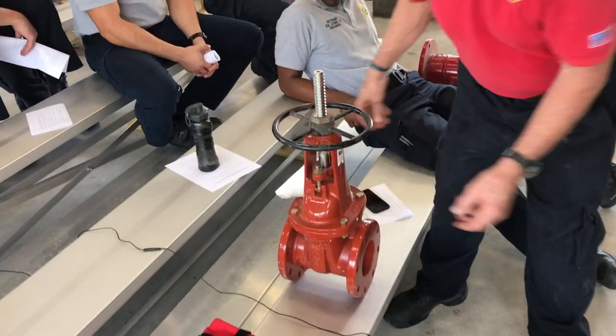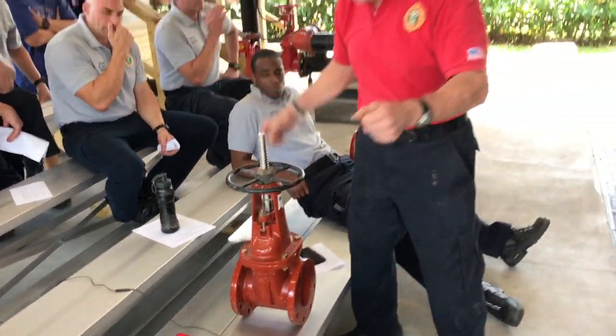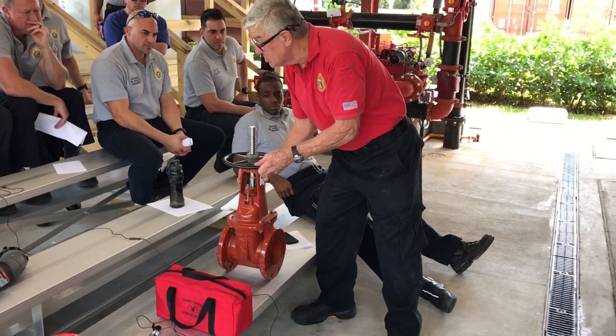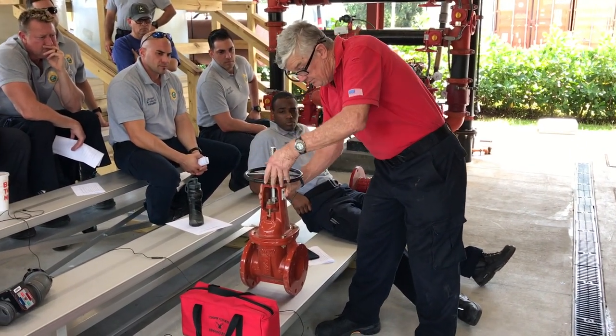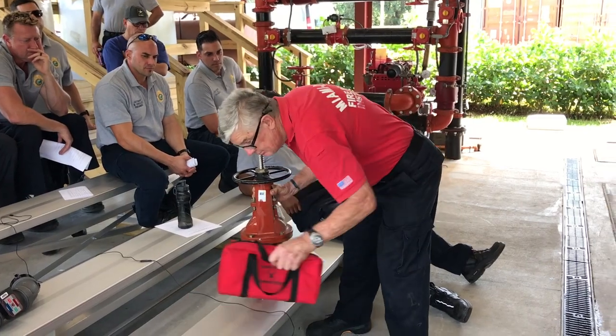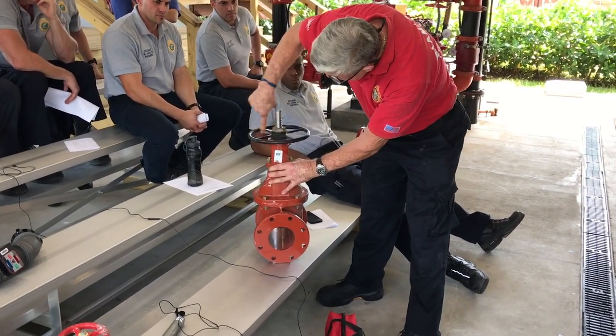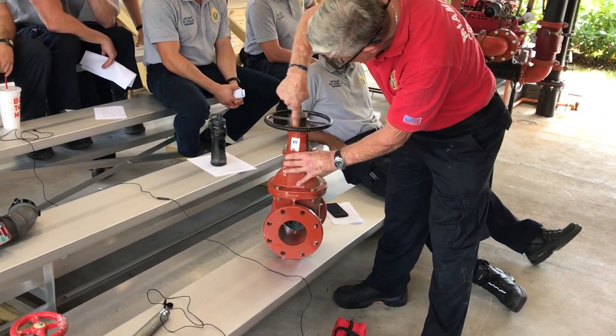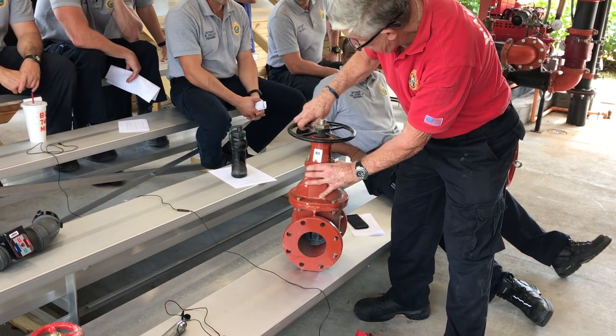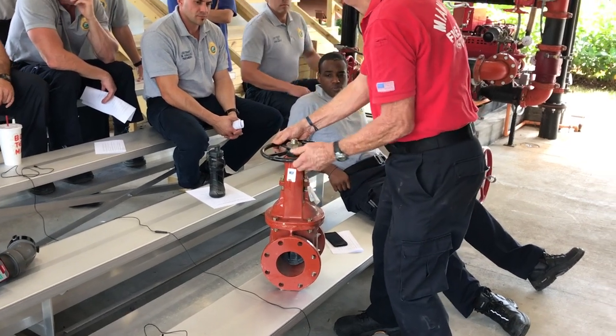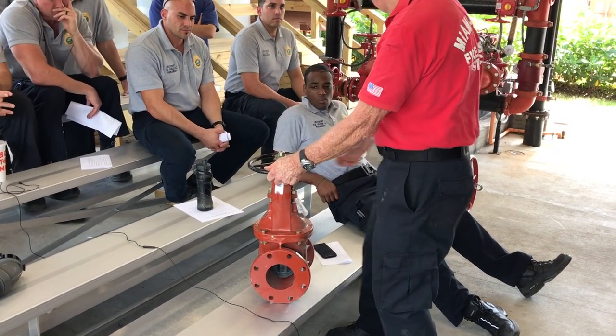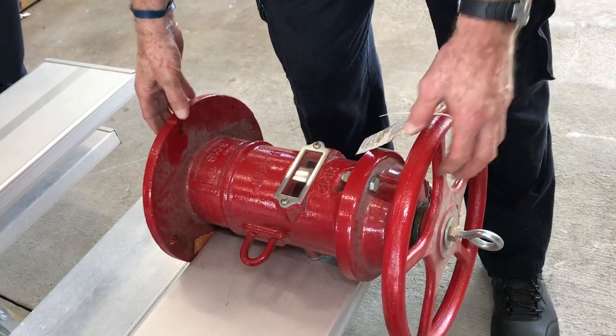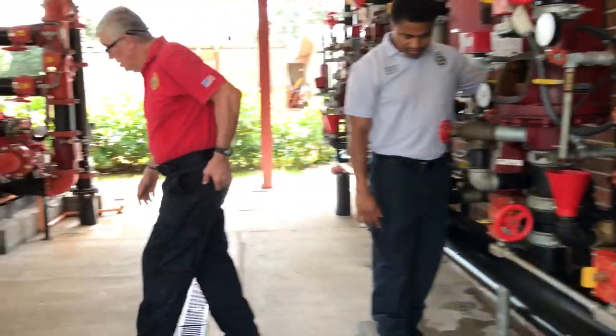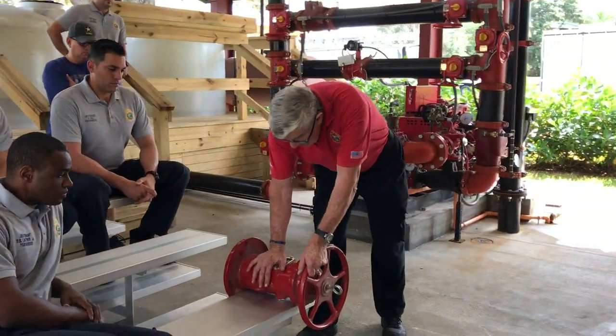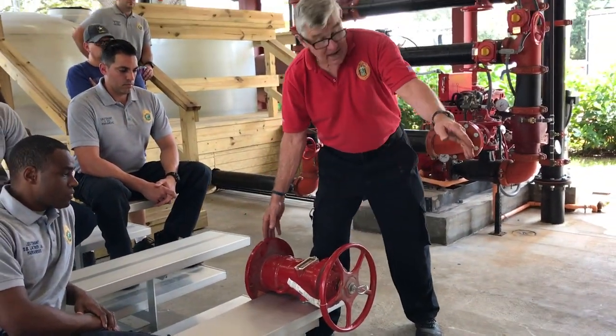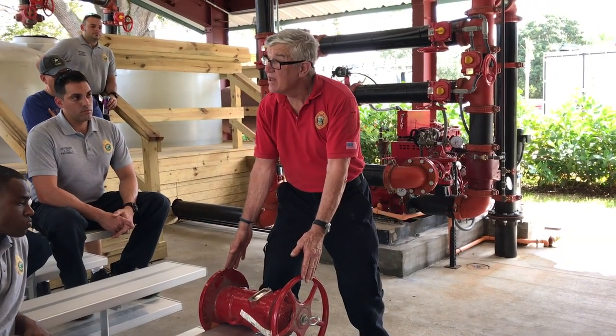This is old school, outside stem and yoke. This one's in beautiful condition. Now, two things, brand new, and there's no pressure behind it. And I know that all of you have control, and sometimes it takes two firefighters. A wall post indicator valve. So in this case, if I wanted to close this valve, and it would have a reach rod that goes through the building. This is on the outside.